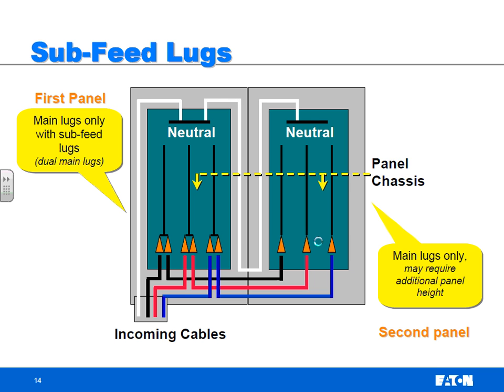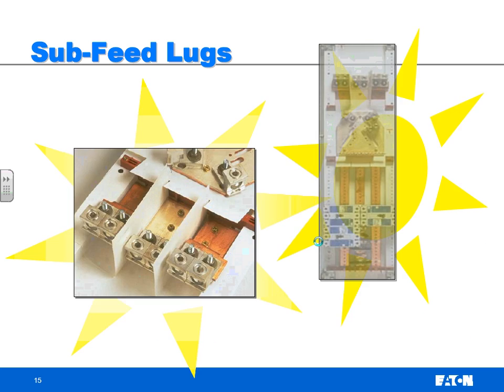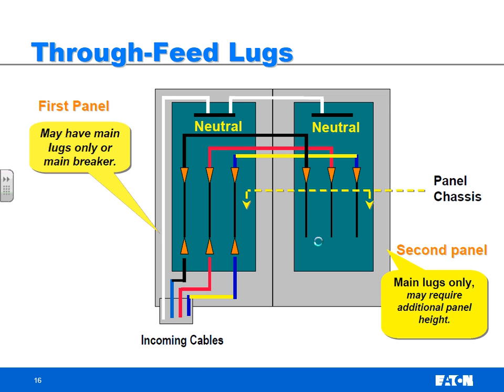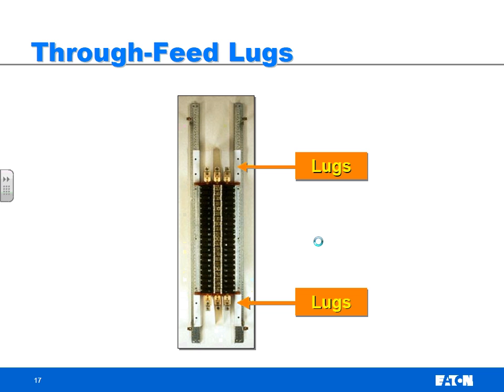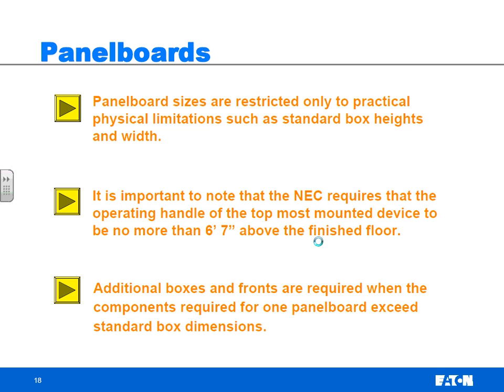Now, that's one lug per phase, but if all of a sudden I had to do 2 lugs per phase at that same rating, I'm going to have to figure out a way to make this circuit breaker bigger, or use something like this to handle this. So generally speaking, that's why we can't do sub-feed lugs on a main breaker. Okay, this is what this will look like, and it's almost a flip, right side up, upside down, lugs on both sides.